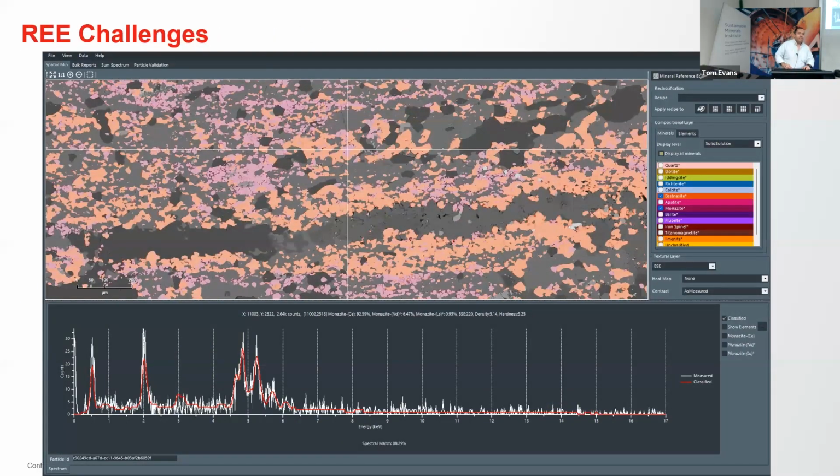And another case that was particularly difficult in the past, and this is becoming increasingly more important and critical, is working with minerals containing rare earth elements. Doing EDS on rare earths, especially large area mapping, was a little bit challenging. If you acquire, let's say, 2,000 or 2,500 counts, the X-ray spectrum is very, very noisy. I have seen worse, for example, in QEMSCAN, where we only acquired 1,000 counts. Sometimes you say, no, this is just noise.